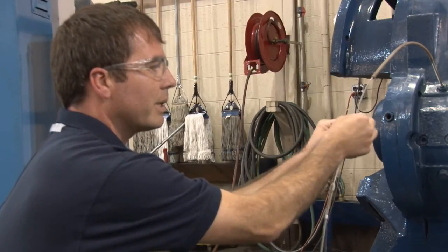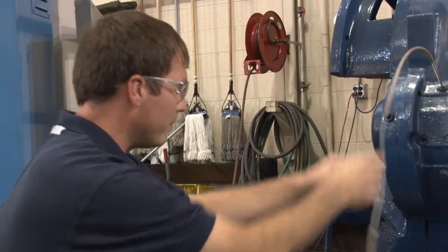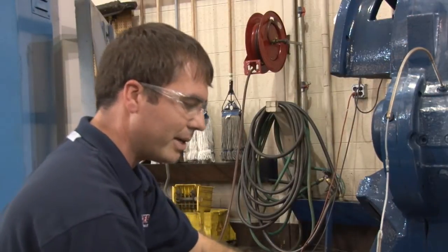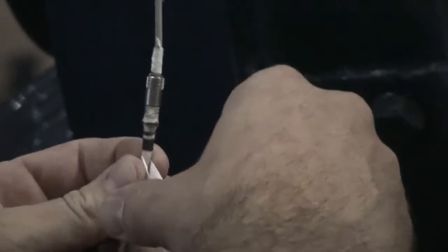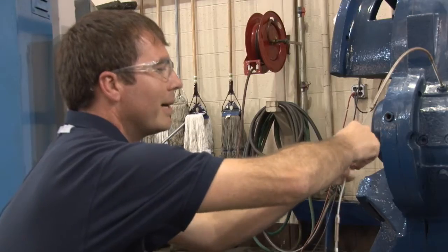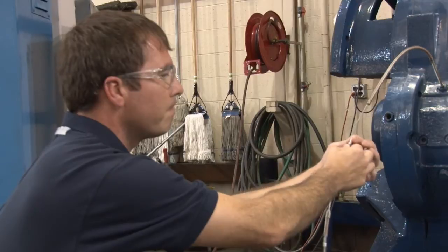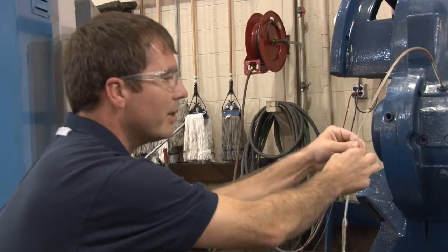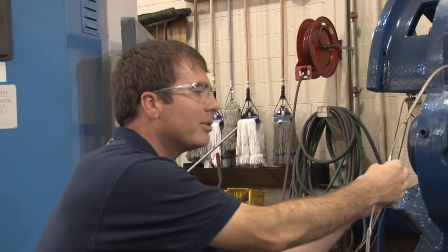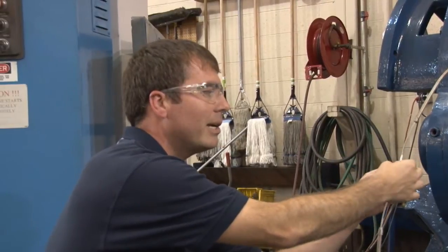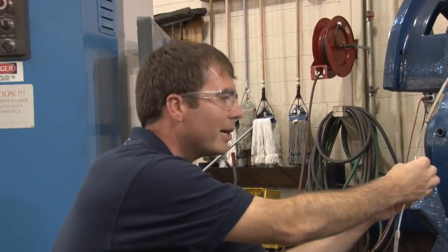Once the connection is clean and tight, we actually take Teflon tape and wrap Teflon tape around the connection. That keeps any oil, any contaminants from getting in the connection.